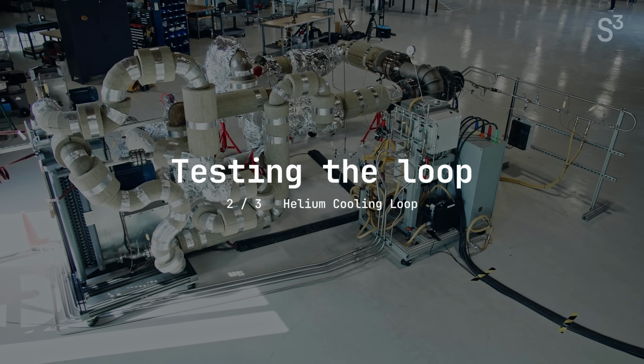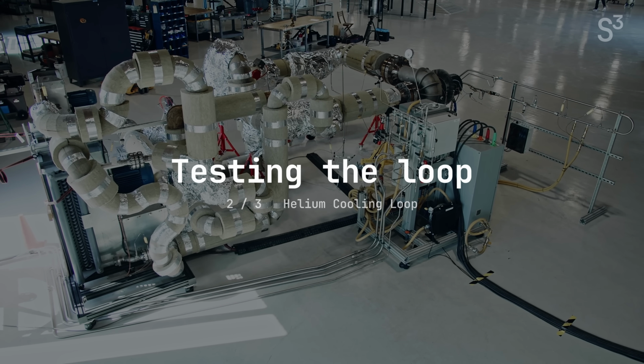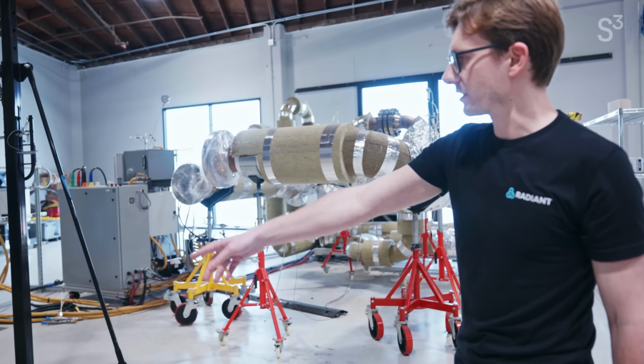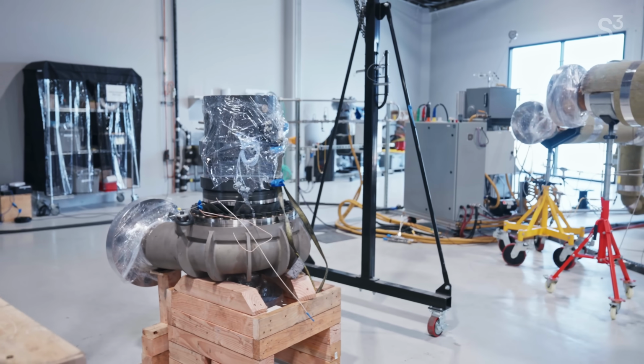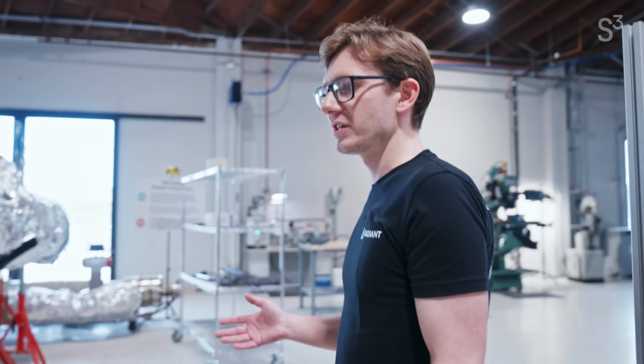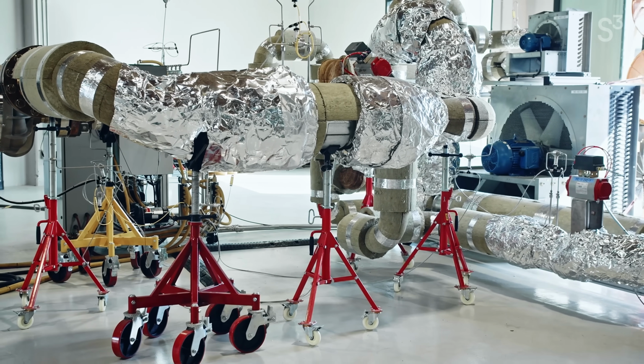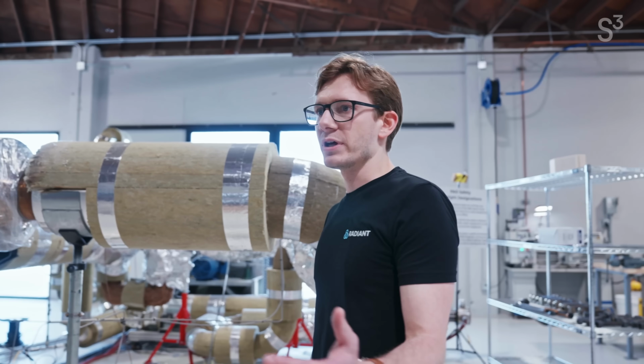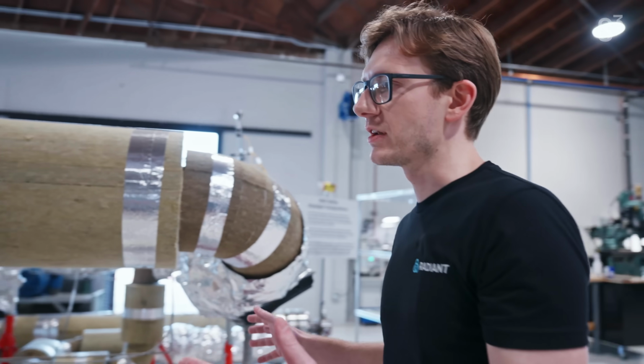Here's our helium test loop. The whole point of that test loop is to test the helium circulator, which is sitting right here right now. This is the first prototype for basically the heart of the helium loop, which is the primary loop coolant. Helium is there to carry heat from the reactor and dump it into our power generation loop. So this is kind of the intermediary.